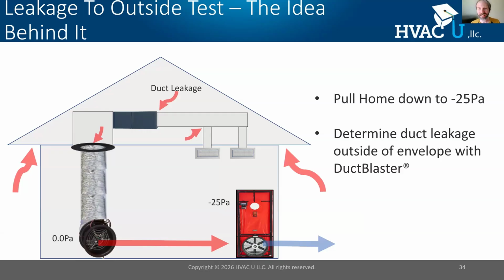I'm glad you brought that up because that is required for Energy Star certification. It's required for LEED. We need to have that whole number. Or again, like we said at the beginning, do ductless mini split or mini splits, and then there's nothing to test, so you eliminate that whole concern. But certainly on existing homes, you're limited on that. So I just wanted to point that out. Oh, good call out, Brett. And I'm a duct person, so what's the fun of not testing the duct system?